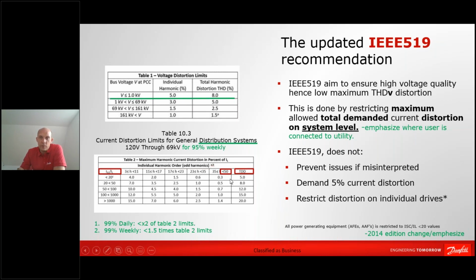How much current distortion you are allowed on the transformer depends a bit on your short circuit ratio. So you need to understand what your short circuit ratio is for your installation to be able to evaluate what the maximum current distortion is. If you look at the lower level here, you have a table showing the maximum allowed current distortion level depending on your system short circuit ratio. If you have a very big transformer, then you will normally see that the short circuit ratio goes up a bit, and that means you are allowed more distortion on a bigger transformer compared to a small transformer. But again, it depends on how much you're loading the transformer.